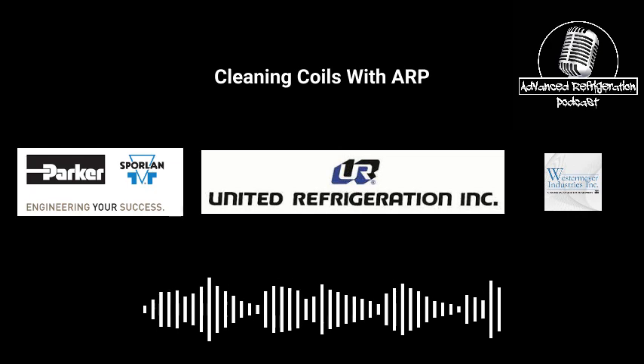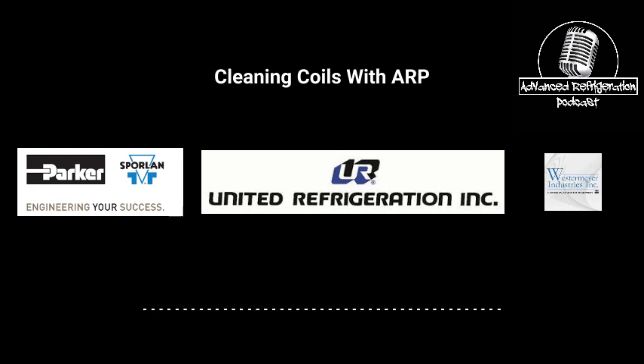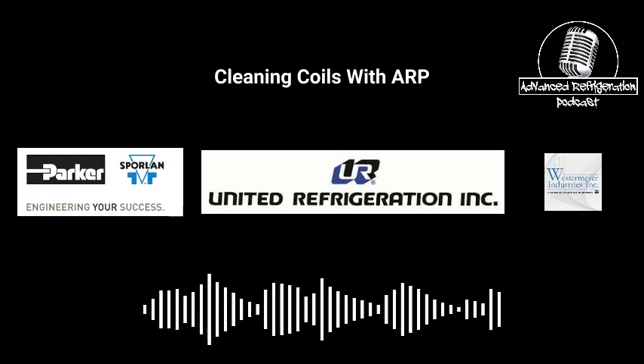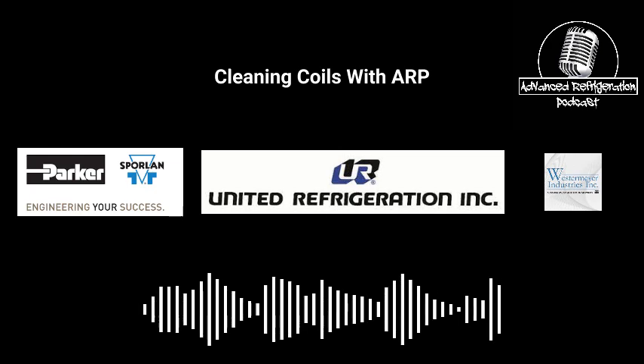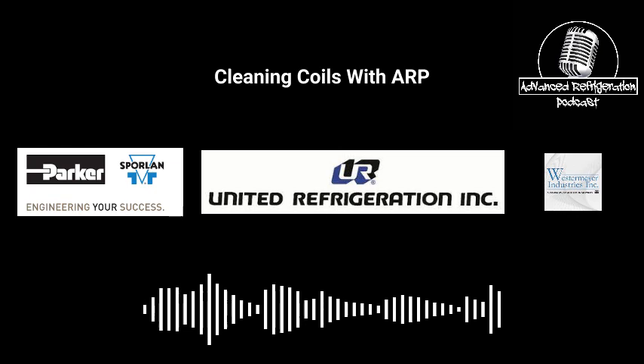I see way too many guys cleaning condensers from the bottom. It sucks, but you've got to pull the fan guard and do it from the top down. Shut the condenser down, pull the top fan guards, and power wash from the top down. If you keep power washing from the bottom up, you're just never going to get that debris out of there.